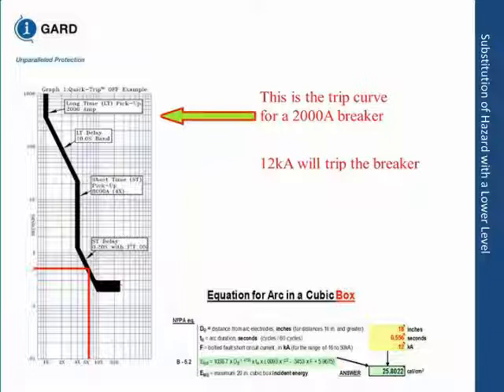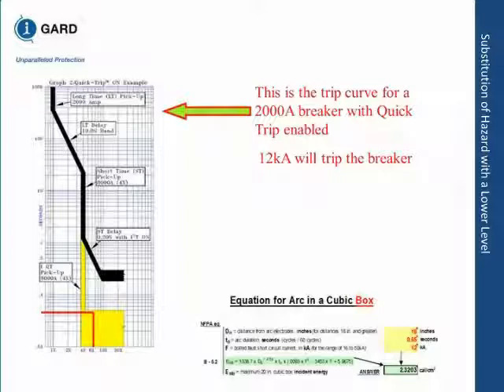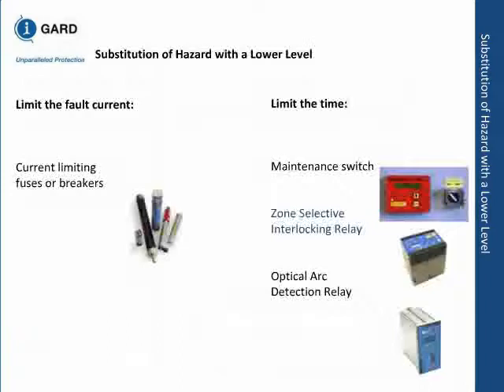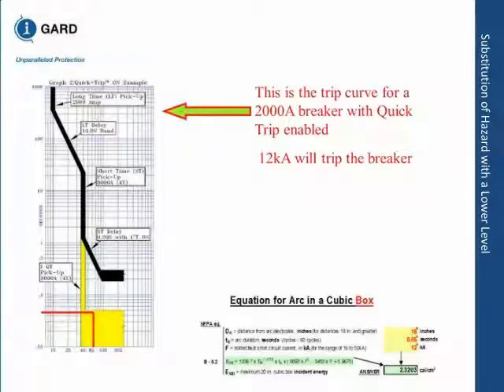Now, if you convert to the maintenance switch, which will trip a lot faster, you can see the energy has gone down to 2.3. That is tolerable. That's an acceptable risk if you have protective clothing on, because the blast pressure may or may not be that high. So basically what the maintenance switch does is reduce the time, clearing the fault faster.